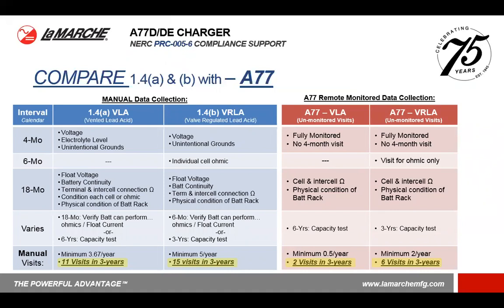We monitor for the voltage. We monitor for the electrolyte level. We monitor for unintentional grounds. So we don't have a 4-month visit. The 6-month visit already wasn't there for a vented lead-acid battery. So at 18 months, we still recommend going back to do the cell and interconnection resistance, as you still have to check the physical condition of the battery rack anyway. So this results ultimately in 2 visits over 3 years on this battery system.